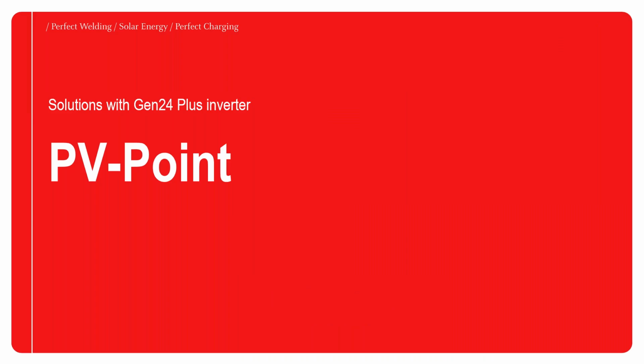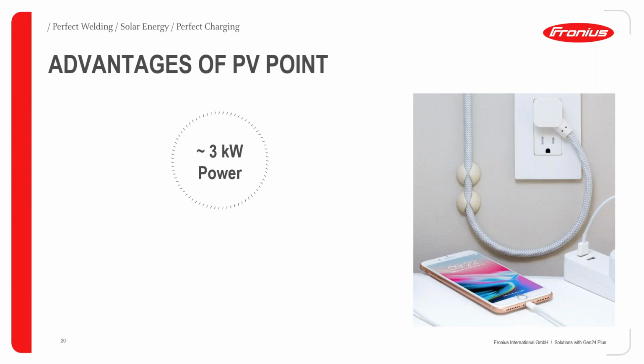Now moving on to the PV points. What are the advantages of PV points? The first advantage of the PV point is that it can give you a 3 kilowatt output when there is no grid available and when you have no batteries installed, as long as you have PV irradiation coming through.